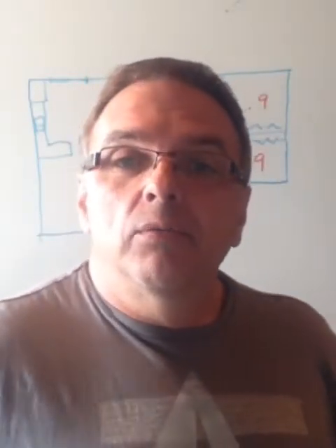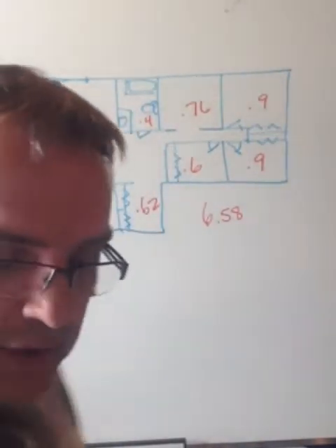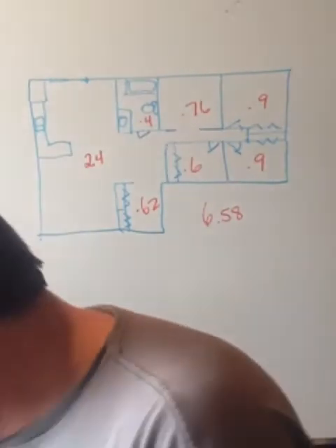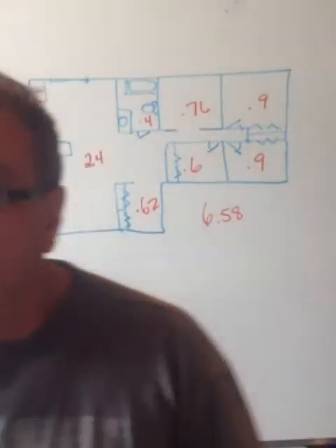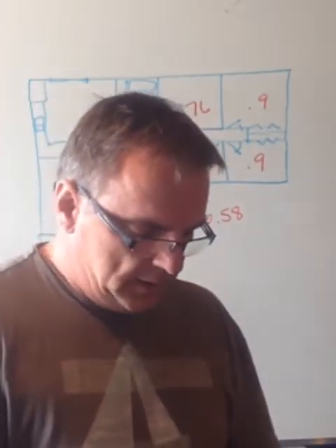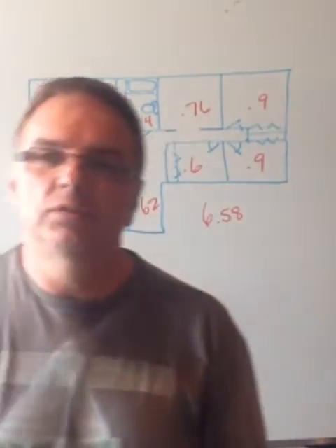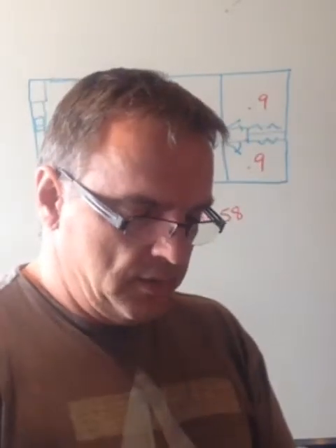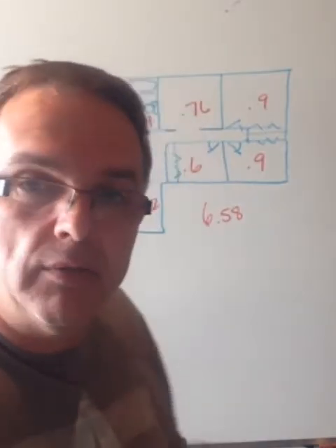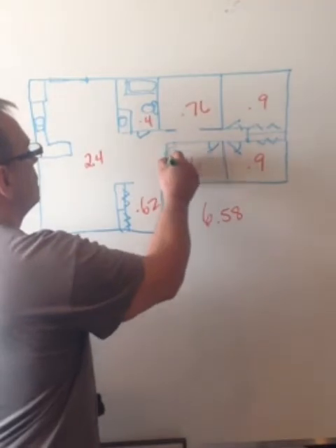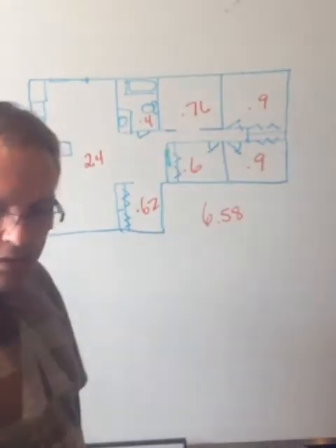So anyway, today I want to take this a little further, what we were talking about earlier, flow rates, and let's have a closer look at this. Now, you've done your heat loss, you have figured out your flow rates per room, etc. Now it's time to do your loop layout, and you locate a manifold, probably in an area such as a closet, right? Like that.